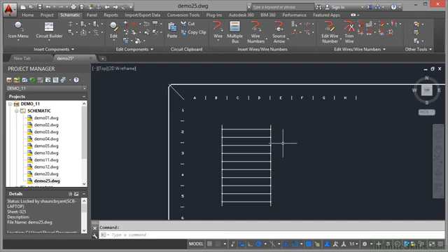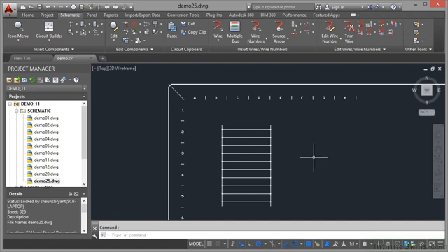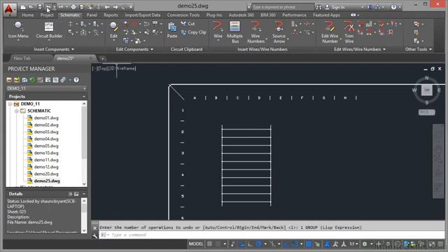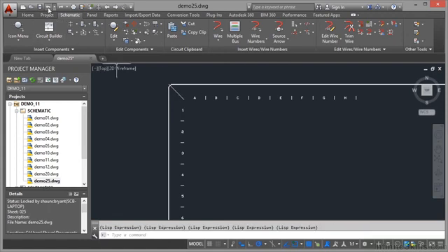That's because you refer to these here so you got B3 will be there and so on and so forth. Ideally what you want to do is you want to set up your ladder so that it actually ties in with the coordinates and the spacings. Now I haven't done that in this case, you can see that that ladder does not tally up exactly with any coordinates on the XY grid. However, other things that come into the drawing can access the grid that we've placed, the XY grid, and can actually have reference numbers associated with the grid. So what I'm going to do, I'm going to undo the ladder, takes a few steps on the undo like that on the quick access toolbar.